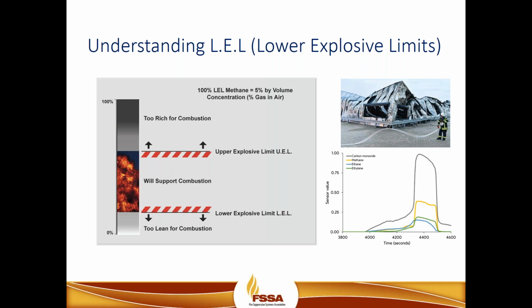Going back to the APS fire, we talked in large part about the methane buildup, and really in order for combustion to occur, we need an environment that allows for the right mixture of oxygen and methane. If the environment's too lean, combustion can't occur, and if it's too rich, combustion can't occur. So we need that critical stage for methane and oxygen to create the explosive combustion environment.